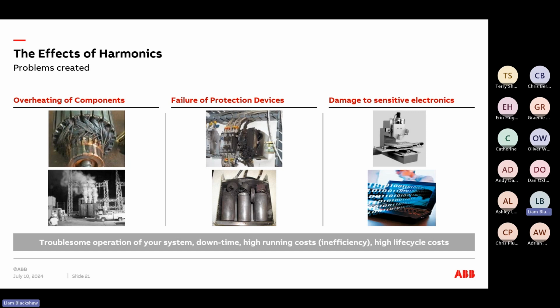Harmonic currents can often expedite the loosening of breaker connections at both line and load sides. So if you've got a loose connection, harmonics could make that condition worse, to a point where we're starting to overheat things and causing failures. This is due to the natural expansion and contraction that occurs, as harmonic currents can increase and decrease with equipment use during certain times of the day, so if equipment is switching on or off at a certain period. Those loose connections will increase the junction temperatures and cause the breaker to trip on what it thought could be an excessive load, when in reality it was a loose connection.